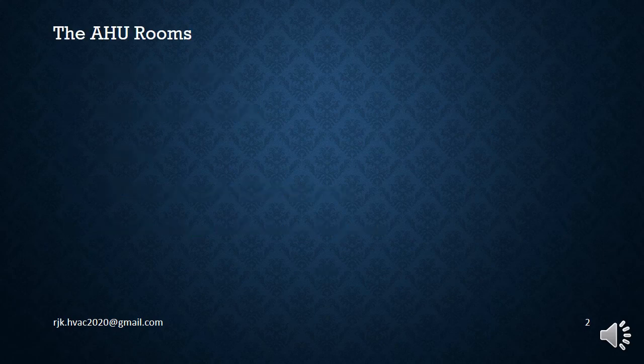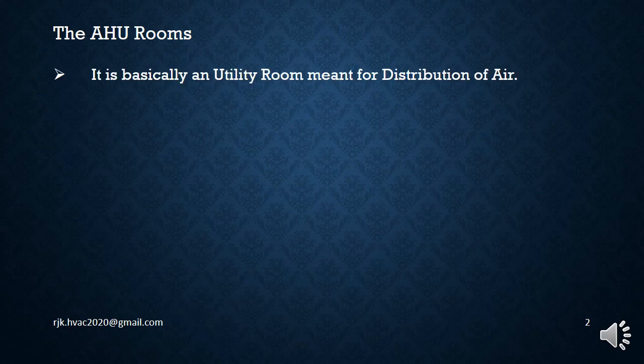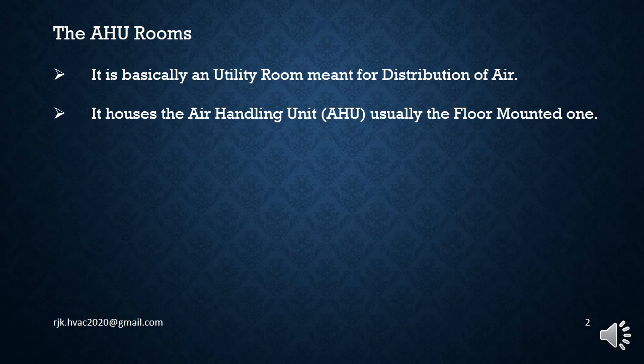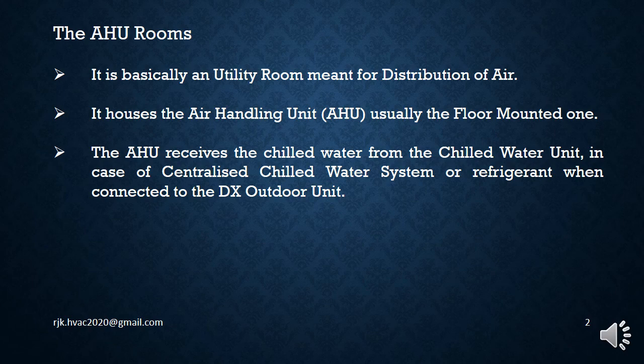In this session, we are going to talk about AHU rooms concerned with the HVAC system. It is basically a utility room meant for distribution of air. It houses the air handling unit, that is AHU, usually the floor mounted one. The AHU receives the chill water from the chill water unit in case of centralized chill water system, or refrigerant when connected to the DX outdoor unit.